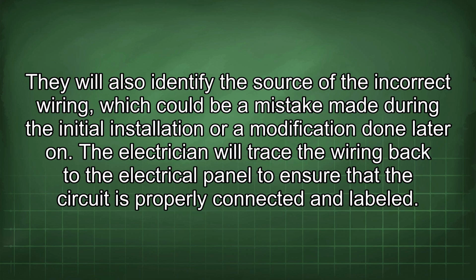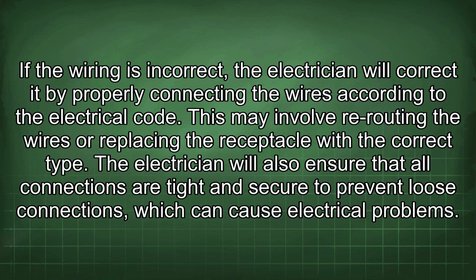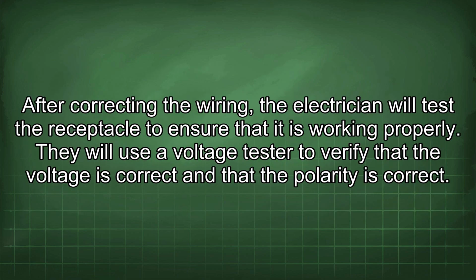The electrician will trace the wiring back to the electrical panel to ensure that the circuit is properly connected and labeled. If the wiring is incorrect, the electrician will correct it by properly connecting the wires according to the electrical code. This may involve rerouting the wires or replacing the receptacle with the correct type. The electrician will also ensure that all connections are tight and secure to prevent loose connections, which can cause electrical problems. After correcting the wiring, the electrician will test the receptacle to ensure that it is working properly.